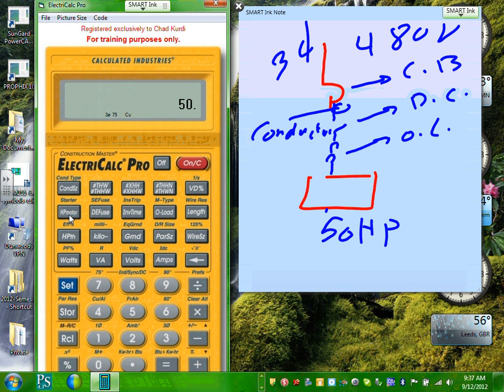Click on this particular horsepower, horsepower motors. I'll tell you the difference between this one and this one. This is the one I'm going to use. Can you see that one horsepower motor? Click on it. You have just told the system that you have an induction motor, which is 99% of your motors. Can you guys see I and D? This is induction motor. 90% of your motors are induction. We can change it to synchronous or DC. 90% is defaulted to induction. So I have a 50 horsepower induction. Can I have thumbs up, Chad? Cool. Now, that's it. That's all you need to do, the horsepower and the voltage.